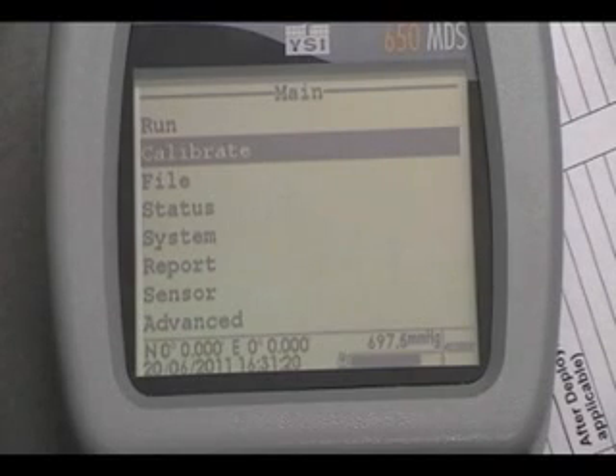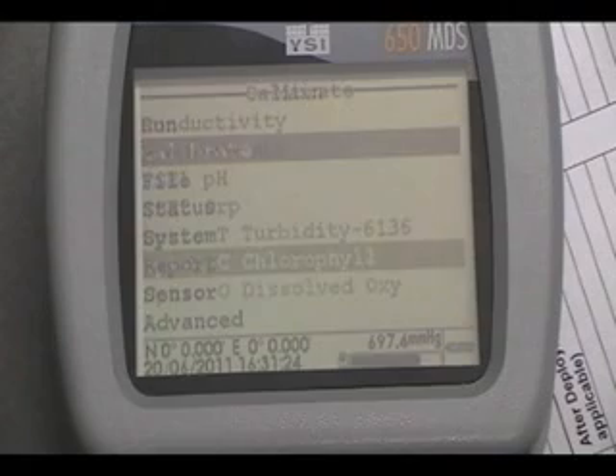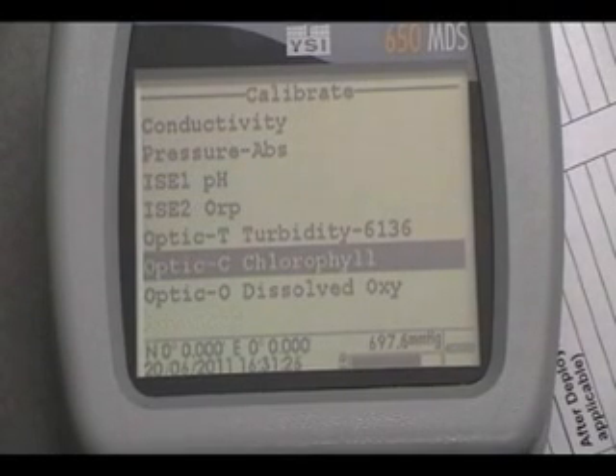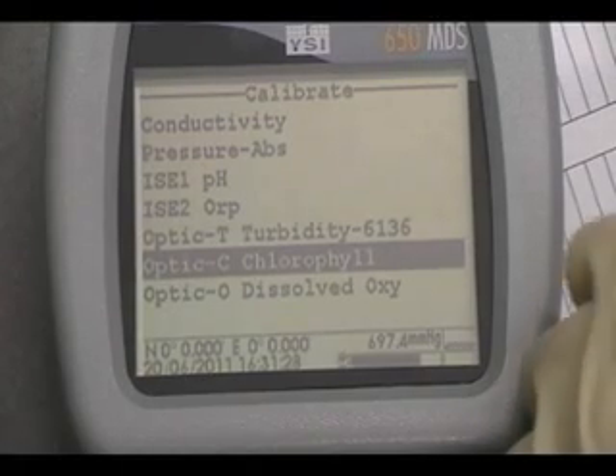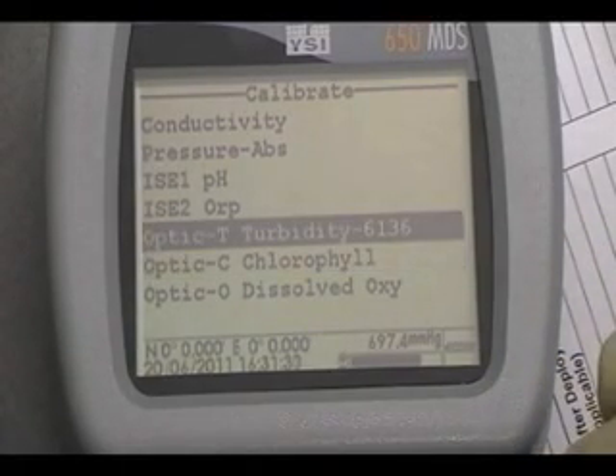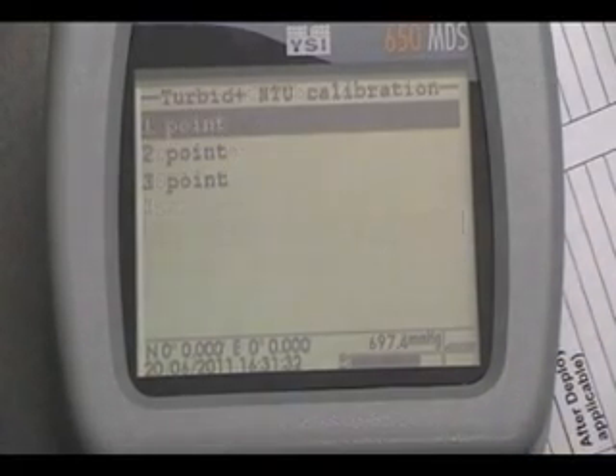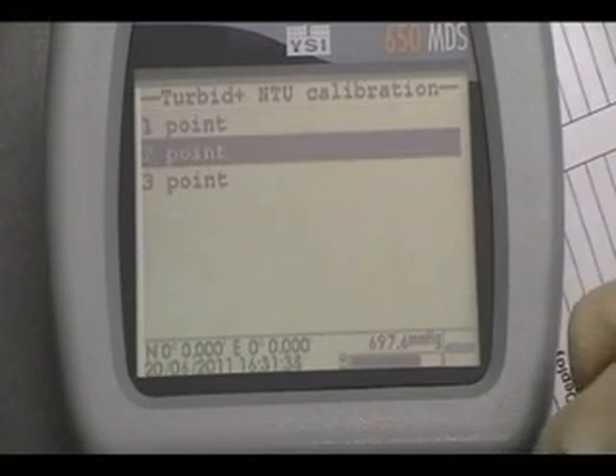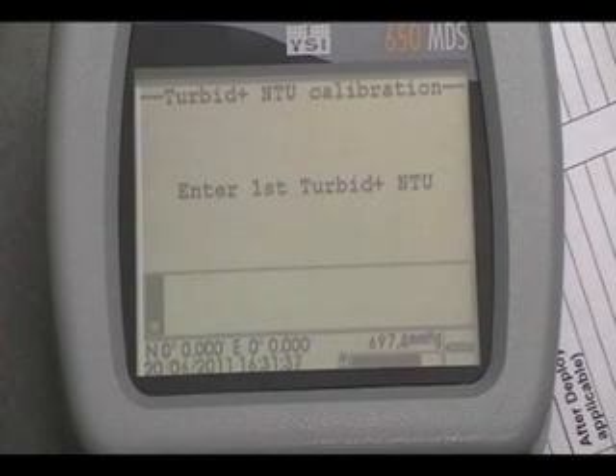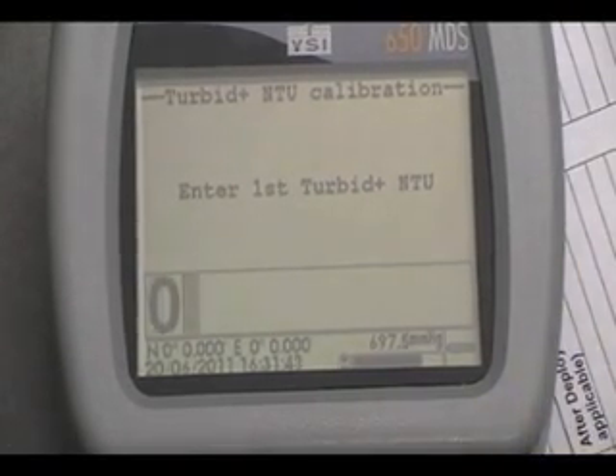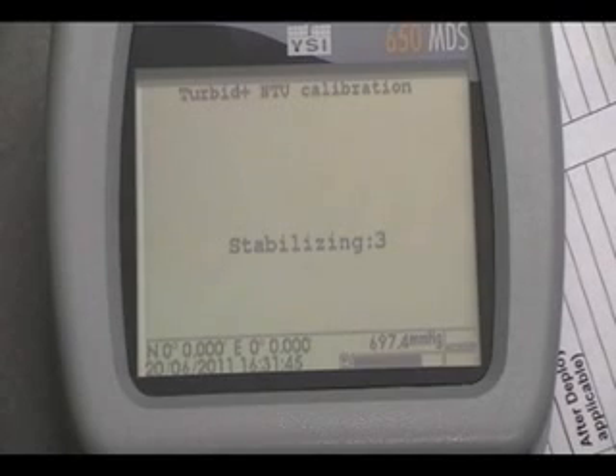Step 4. From the Sonde menu, select Calibrate and press Enter. Step 5. Select Optic T Turbidity and press Enter. Step 6. Select 2 point. Press Enter. Step 7. Input the value 0 at the prompt and press Enter. The screen will display readings.